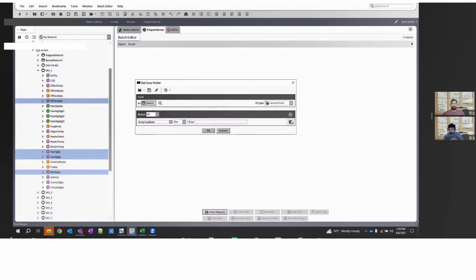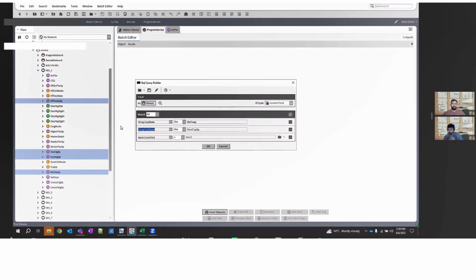Instead of defining one point, I'll use display name and define it here, like change this to room temp, OCC cooling SP. It's not just one point that we can discover here. I'll also paste display name like OCC HTGSP. The only thing to change here is the condition match, which means all conditions should match, so it will search for a control point where the display name is room temp, occupied cooling set point, and heating set point all at once, which won't give an answer.